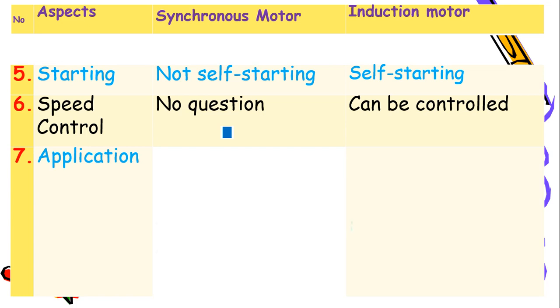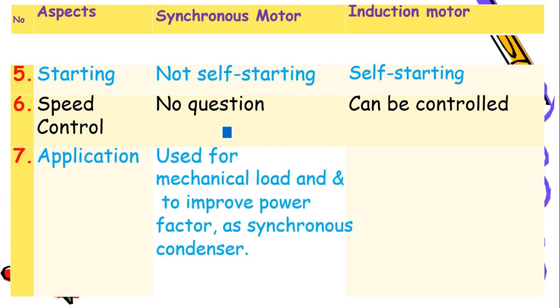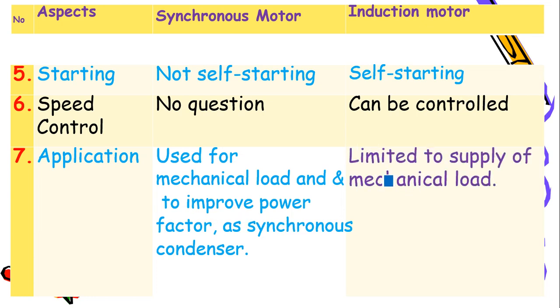Now here application. The synchronous motor is used for mechanical load as well as to improve the power factor. The synchronous motor will be used as synchronous condenser to improve the power factor as we remember. But the induction motor, it is only limited to use to drive the mechanical load only. There is no other requirement for that.